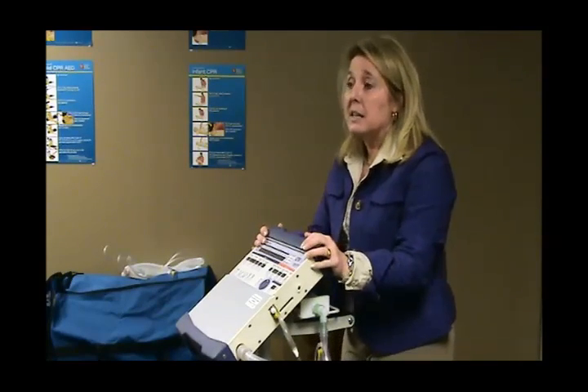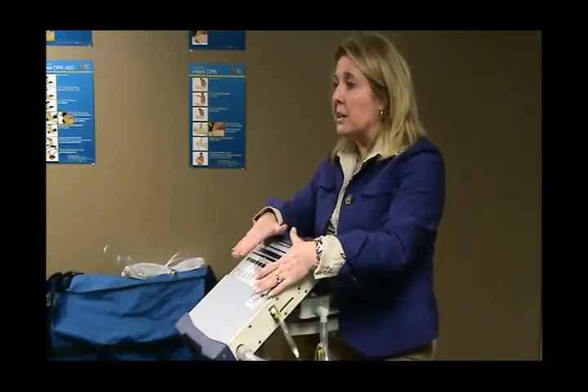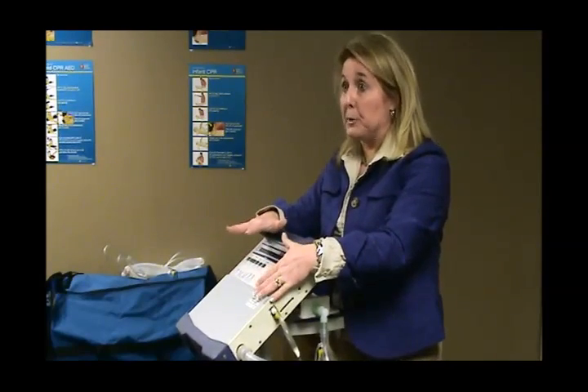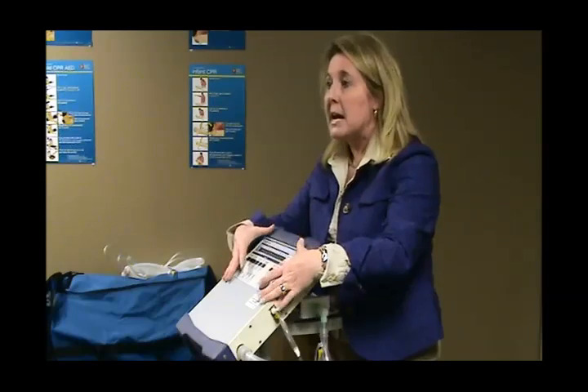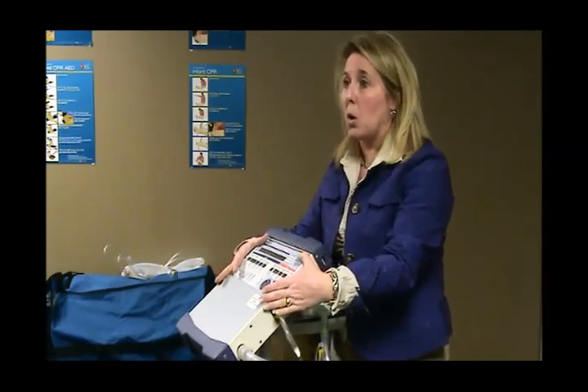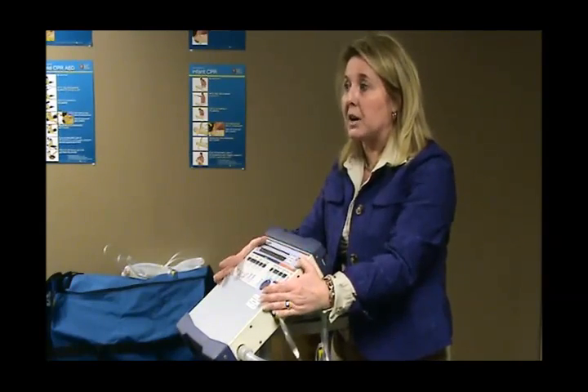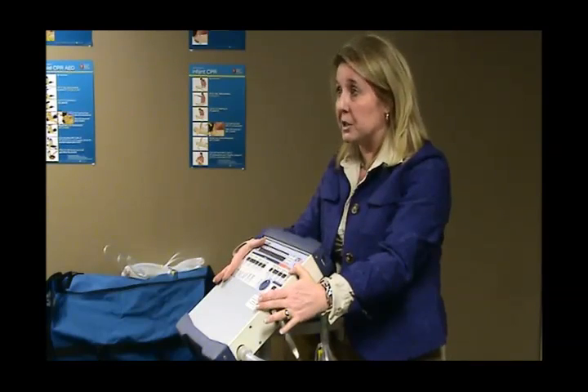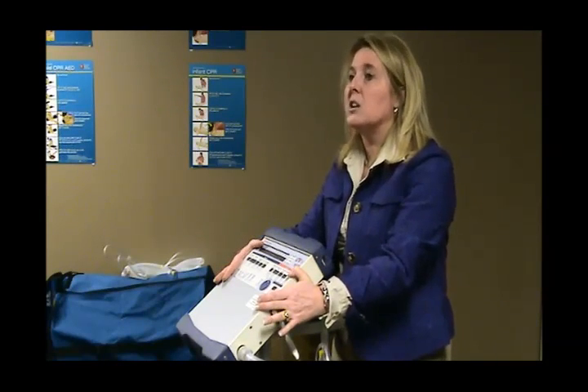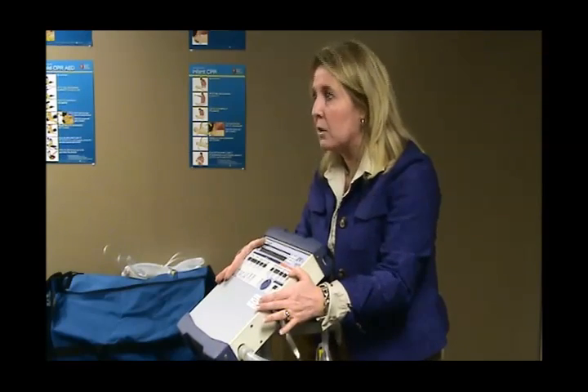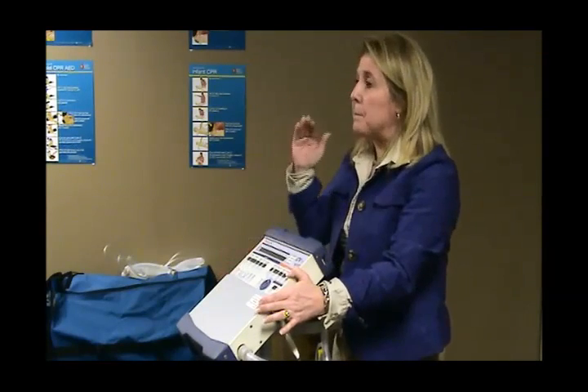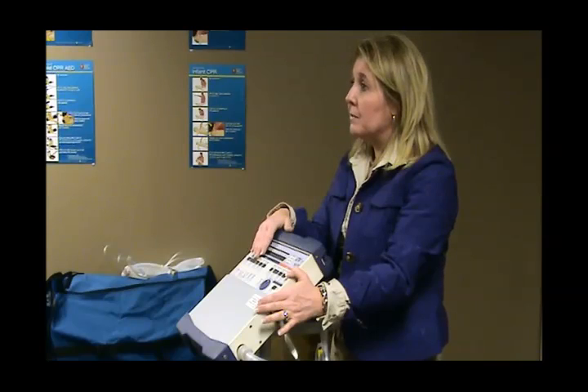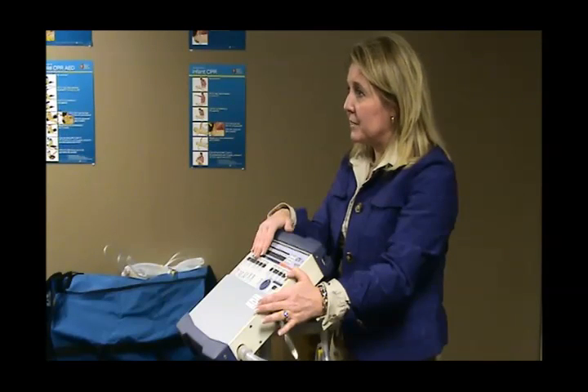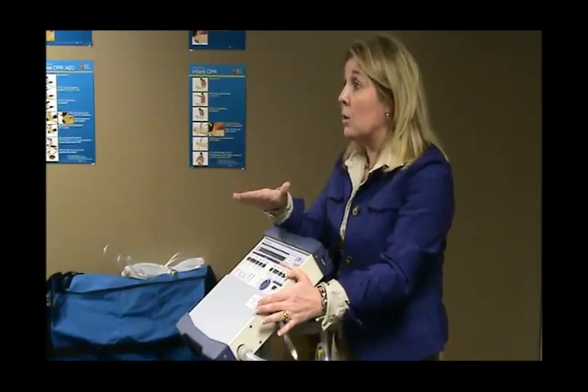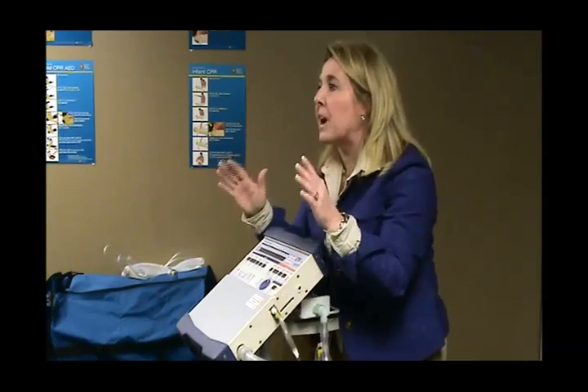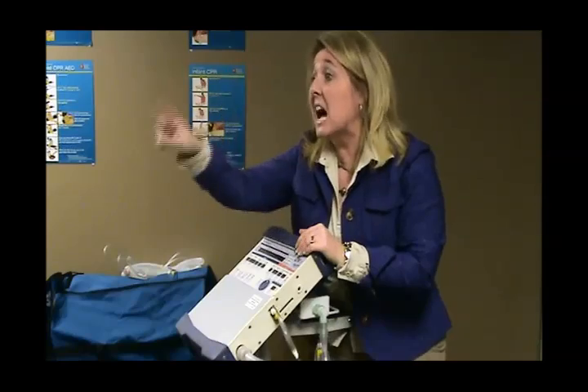Now, I will say this, and I rarely make comment on other people's ventilators because it's just not my place to do that. But there's a brand of ventilator out there from Respironics, it's called the Trilogy. You may see these ventilators, they are essentially a glorified BiPAP, okay? They work like a BiPAP. Well, I had a client that had it as a BiPAP, but then she had to get a trach, and that's what she's still using. And it is FDA approved for that. Okay, so it is FDA approved for that. But it operates like a BiPAP, meaning it is not PEEP compensated.